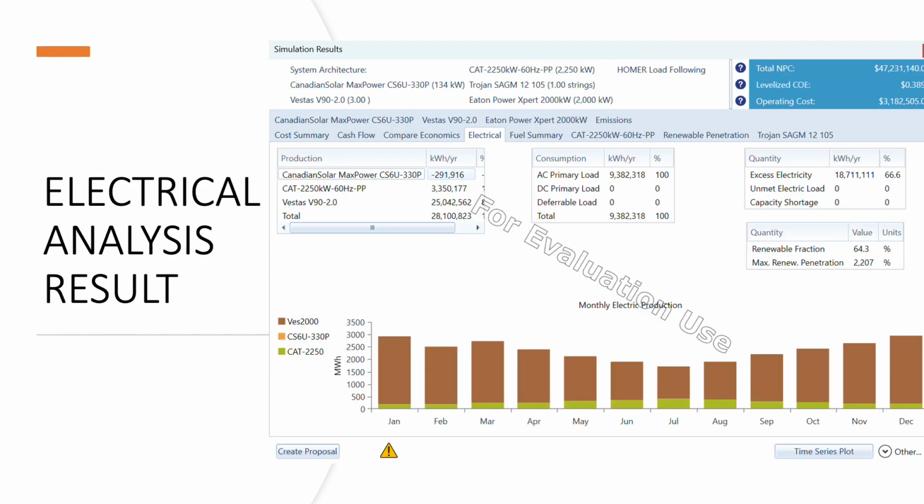During our optimization analysis, the best optimized result shows that the wind turbine provides 91% of the needed energy. The diesel power plant provides 8.75%, while the PV provides 0.225% of the needed energy. The levelized cost of energy is about $0.389, which is cheaper compared to the current cost of $0.7, which is being paid by the residents of Nain, Labrador when all profits and overhead costs are added.